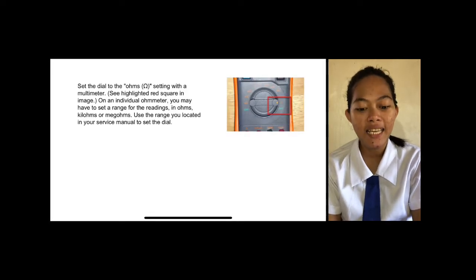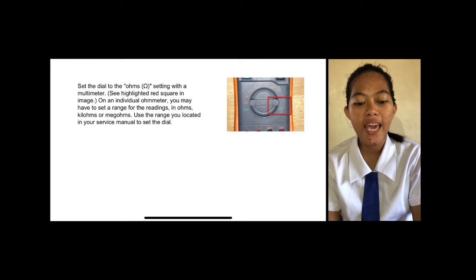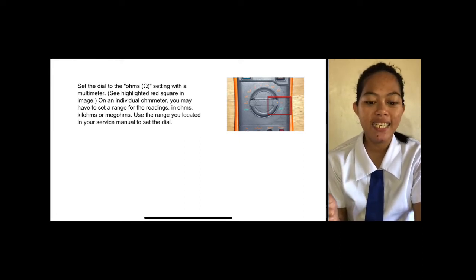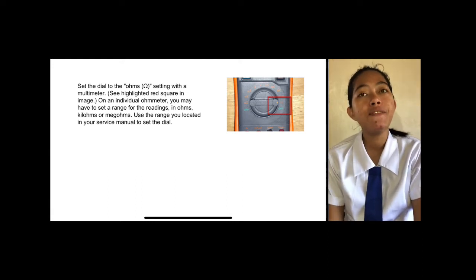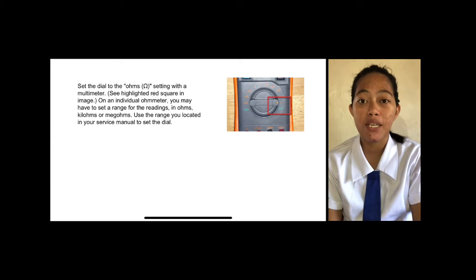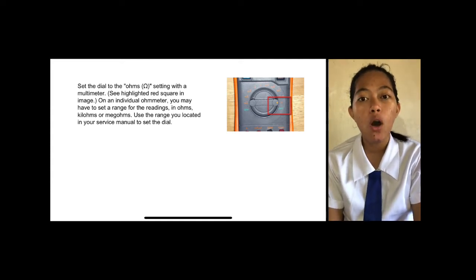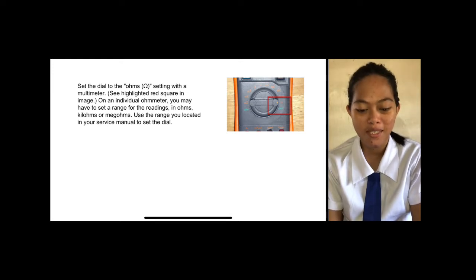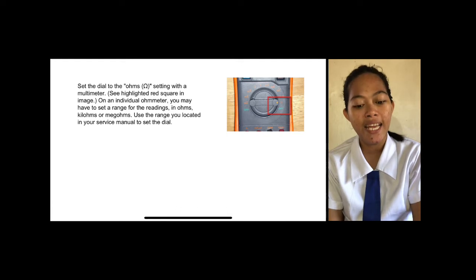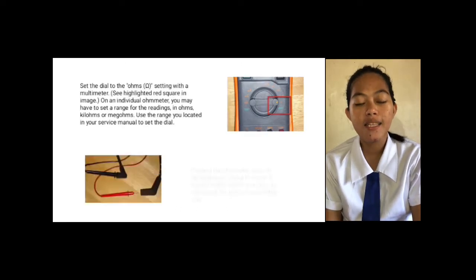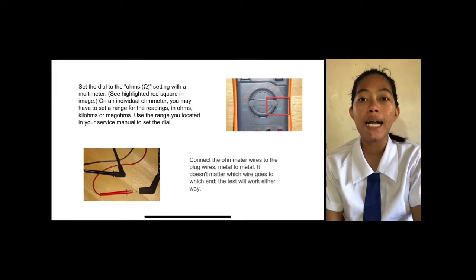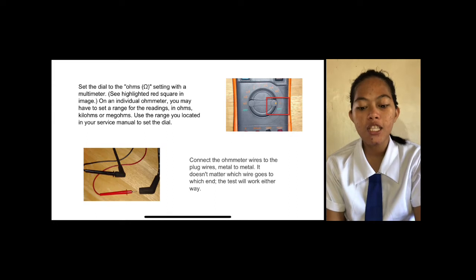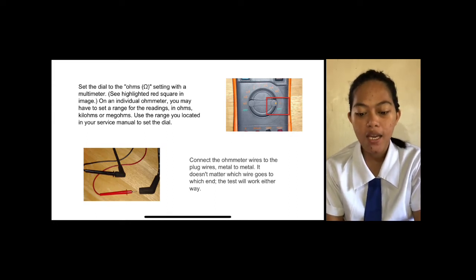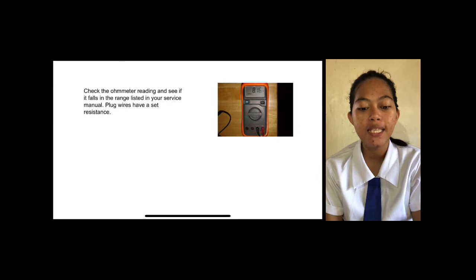Set the dial to the ohms setting with a multimeter. See the highlighted red square in the image. On an individual ohmmeter, you may have to set a range for the readings, in ohms, kilo ohms or mega ohms. Use the range you located in the service manual to set the dial. Then connect the ohmmeter wires to the plug wires, metal to metal. It doesn't matter which wire goes to which end; the test will work either way. Check the ohmmeter reading and see if it falls in the range listed in your service manual.